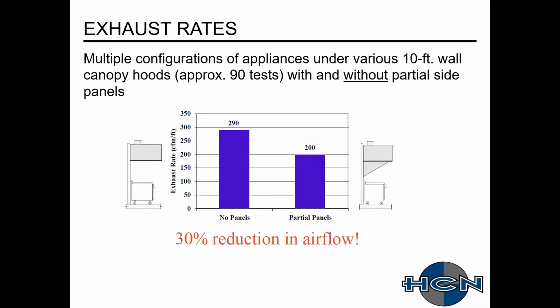Hey, Jeremy. Yeah. Why wouldn't you use end panels for all hoods to reduce the total airflow? You should, as a design, we should be doing that. The only time I would say it's hard to do would be those double island canopy hoods or islands in general, because you've got people running back and forth, and if you have an end panel there, you could technically run into something.